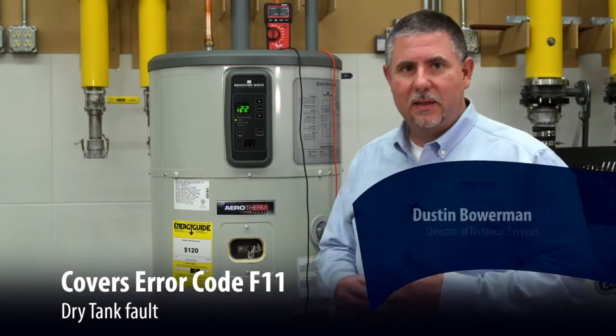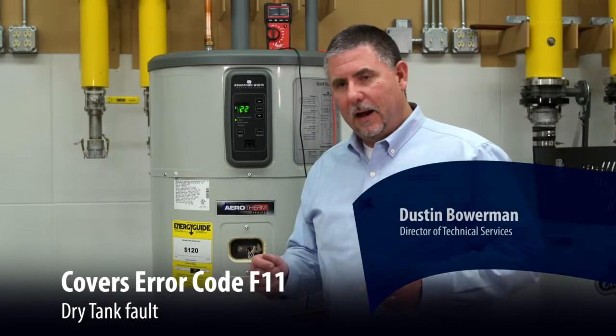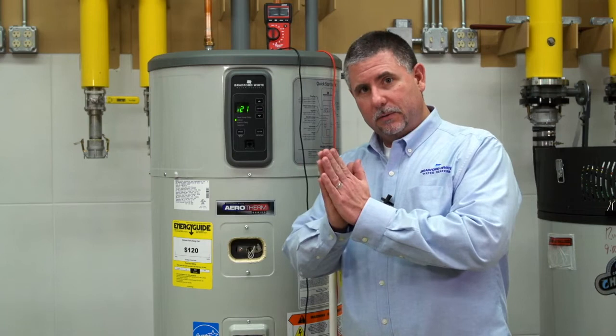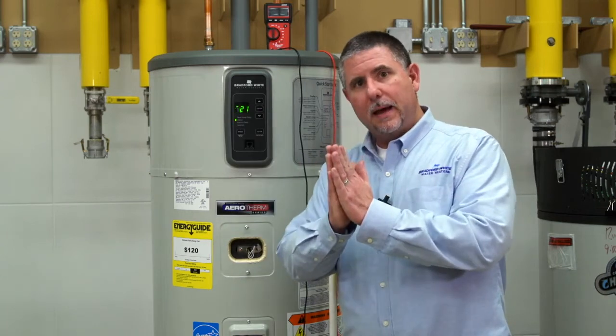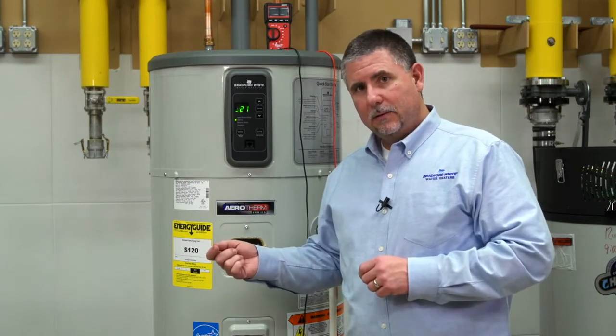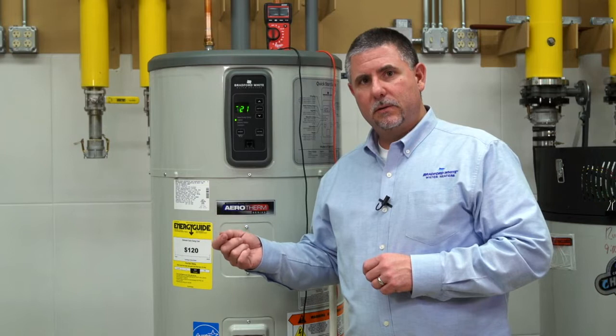In the unlikely event that you get error code F11, that's telling us that the control doesn't recognize there's water in the tank. So through the commissioning process, the T2 sensor is monitoring tank temperature. Okay, tank temperature, and then you have water on the back side of that. During the commissioning process, and the heat pump system is running, the control monitors how quickly that tank is heating up. Without water in the tank, it's going to go much faster, meaning you heat air quicker, easier than you do water.